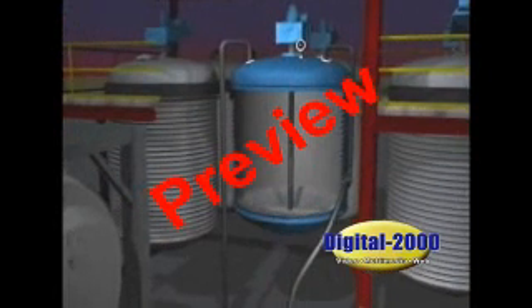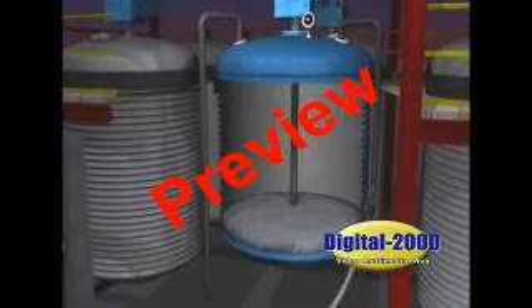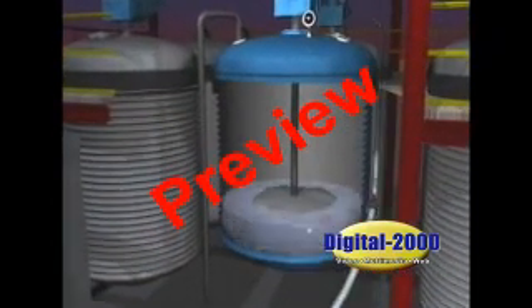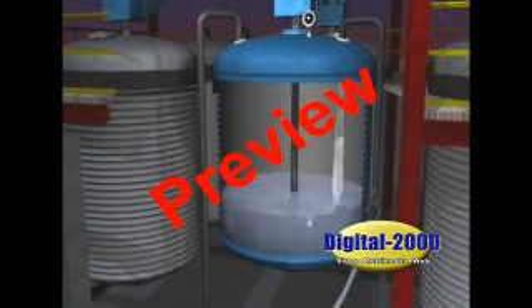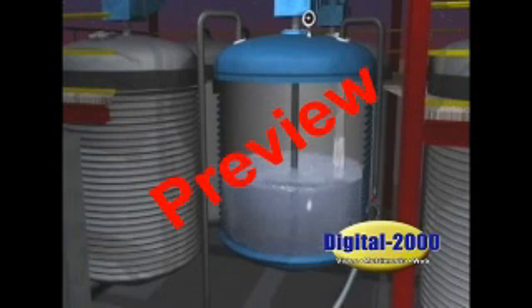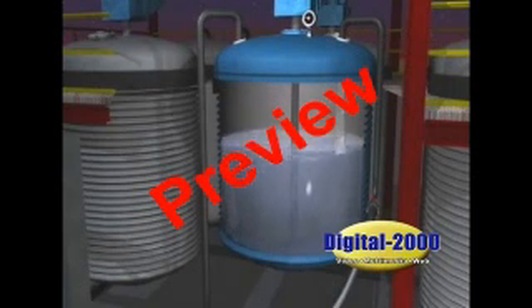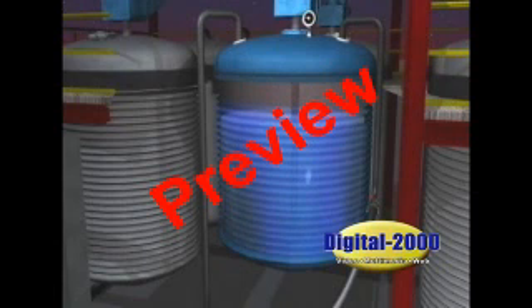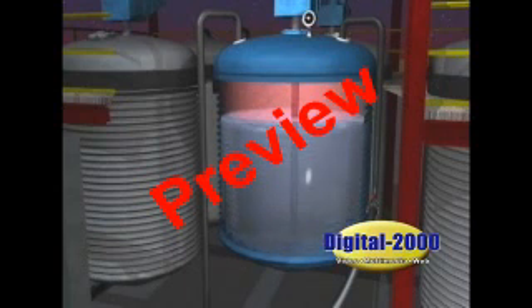Starting the production process for the first time, operators loaded the large vessel with all of the cyanuric chloride powder and the catalyst. They then added all of the allyl alcohol and began mixing the chemicals. To control the temperature, MFG had rented a portable chiller and connected it to the cooling jacket on the vessel. But as soon as all of the raw materials were combined, the reaction began producing heat faster than the cooling system could remove it. The temperature increased uncontrollably, and with all of the raw materials already in the vessel, nothing could be done to control the reaction.